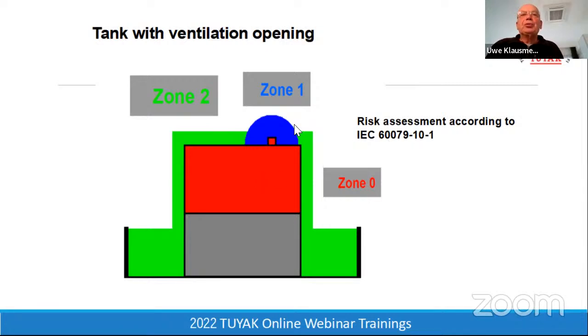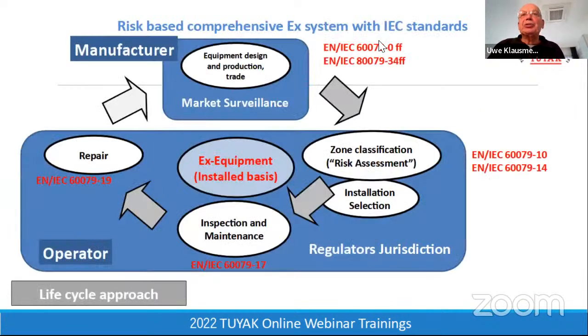Then you have to be aware that around the ventilation opening of the tank, there is a zone 1. That means you need to install equipment made according to EPL 2, equipment protection level 2. And for zone 2, you need equipment protection level 3. This is all to be found in the related standards, which you can see here for the marking.